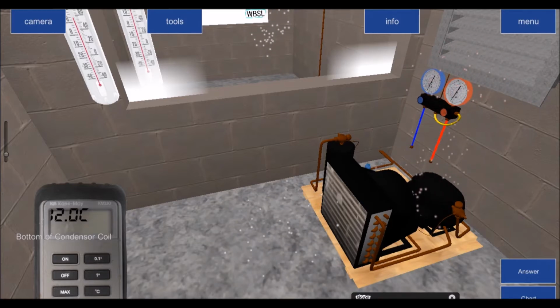Well, it's the difference between my condensing temperature, as read from my high side gauge if I had a gauge fitted, or my condensing temperature as read from the middle of my condenser, and the temperature of the liquid as it exits the bottom of the condenser. In this case, there's 6 degrees. That's the subcooling value. And again, as I said to you last week, subcooling value should be a difference of between 4 and 7, and superheat value should be a difference of between 5 and 8.